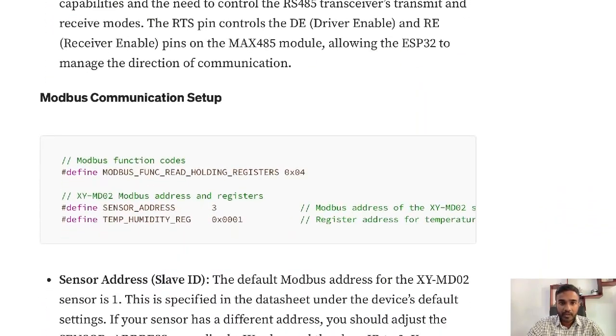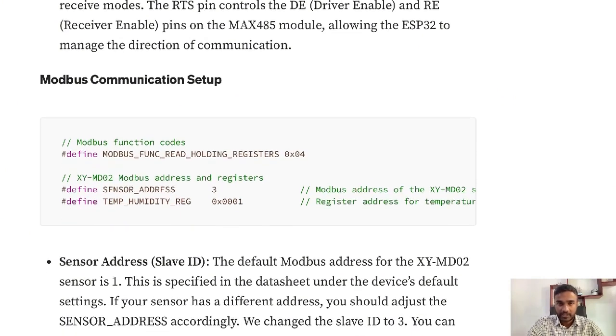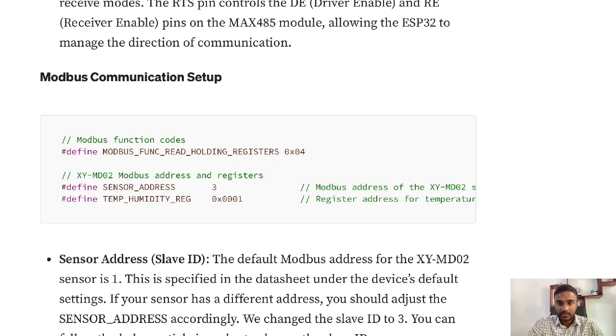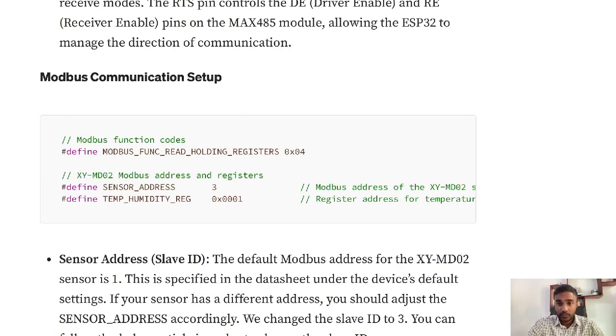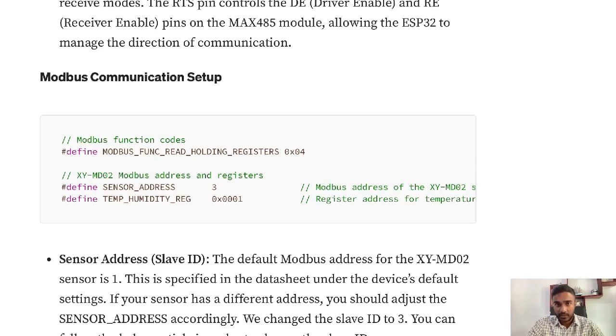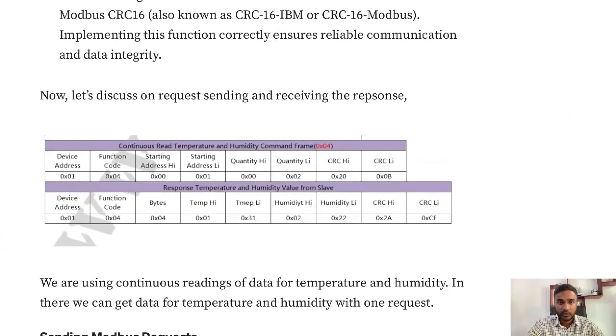After that there's a set of things you need to add in the function code: the sensor address and the register address. The function code is taken from the datasheet, and the sensor or slave ID is also taken from the datasheet, but you can change it if needed. There's separate software to change it. The register address is related to the parameters. For temperature and humidity there's a separate register if you take it as a continuous stream, but if you need temperature alone you can have a separate register, and if you need humidity alone you can use a separate register. You need to use the datasheet to get it.